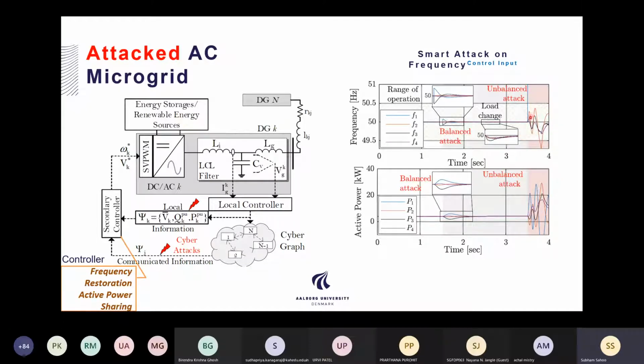After some time, when you unfairly increase the frequency attack elements, it actually goes outside the range of operation. This is where your circuit breakers are waiting to operate, and you can see that within no time, 2 of your converters are already lost here, after 3.5 seconds.